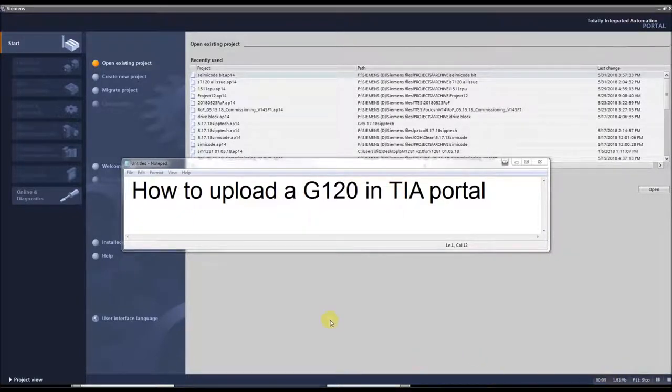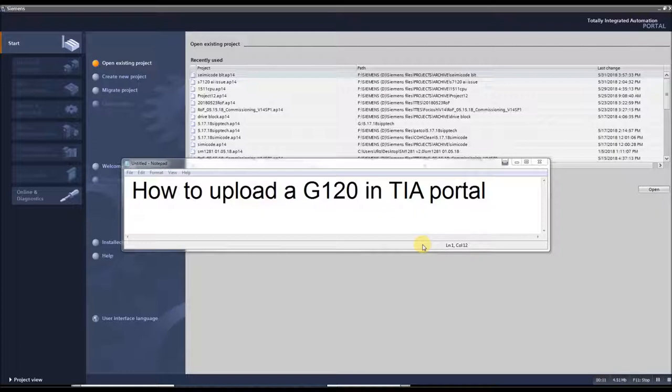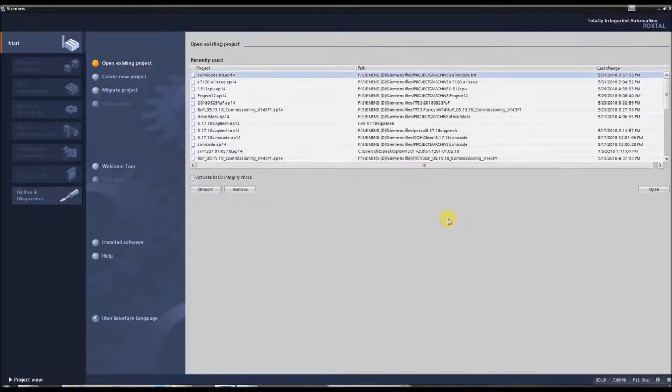Today I'm going to show you how to upload a G120 into TIA Portal. So first, open up TIA Portal, turn on your VFD, connect an Ethernet cable from your PC to the G120, and let's get to it.